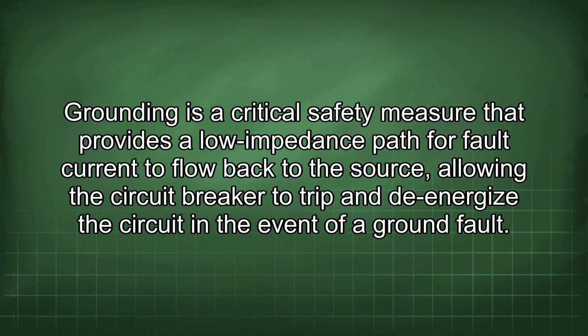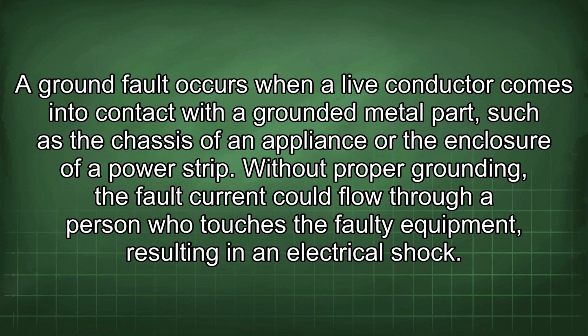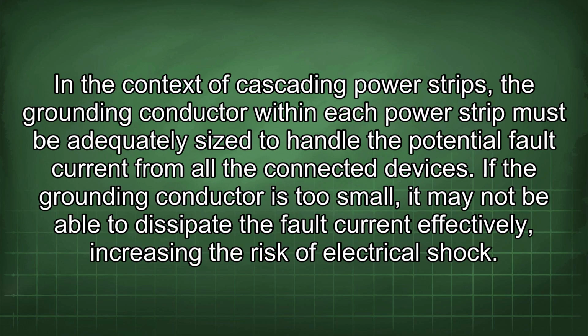Grounding is a critical safety measure that provides a low impedance path for fault current to flow back to the source, allowing the circuit breaker to trip and de-energize the circuit in the event of a ground fault. A ground fault occurs when a live conductor comes into contact with a grounded metal part, such as the chassis of an appliance or the enclosure of a power strip. Without proper grounding, the fault current could flow through a person who touches the faulty equipment, resulting in an electrical shock. In the context of cascading power strips, the grounding conductor within each power strip must be adequately sized to handle the potential fault current from all the connected devices. If the grounding conductor is too small, it may not be able to dissipate the fault current effectively, increasing the risk of electrical shock.